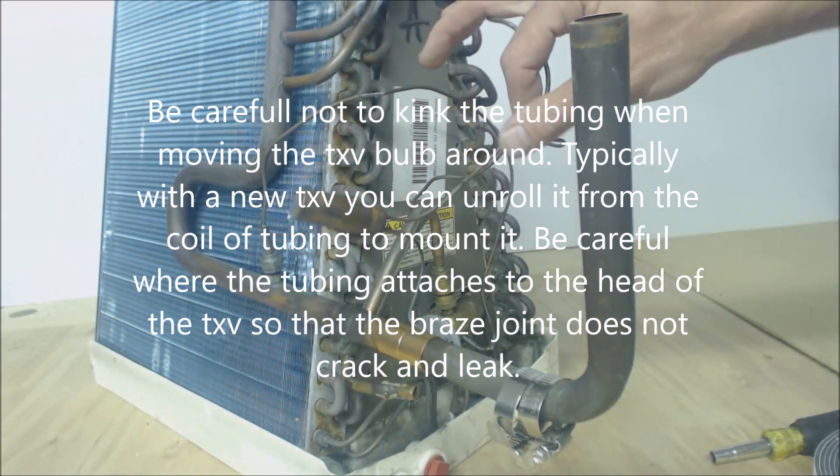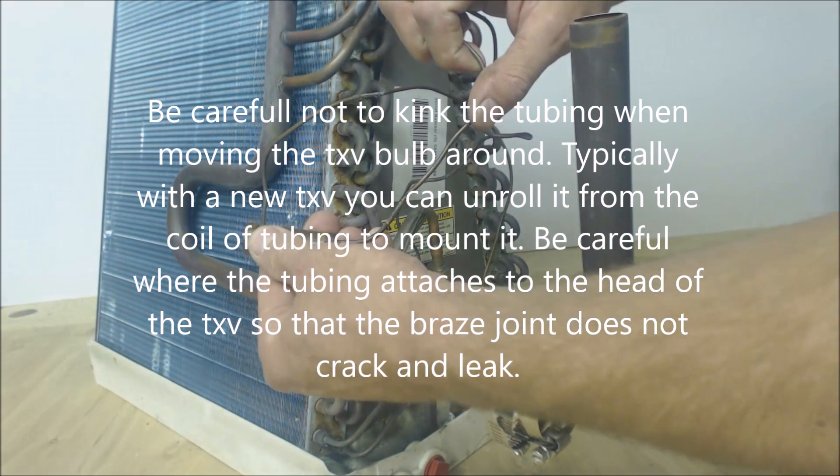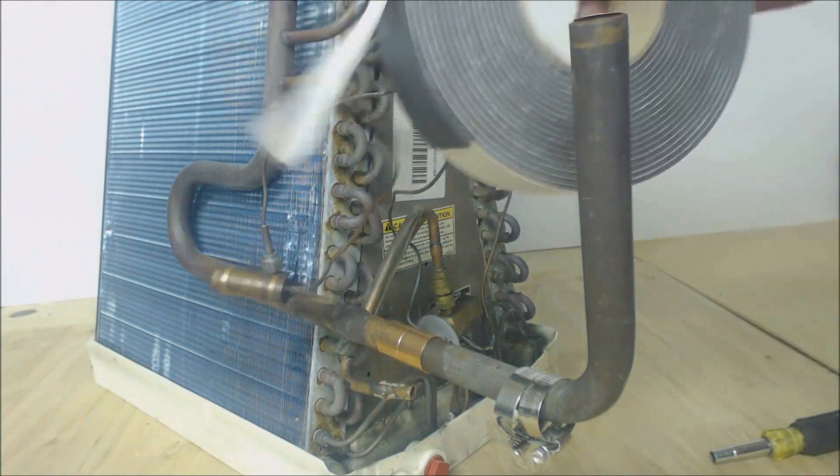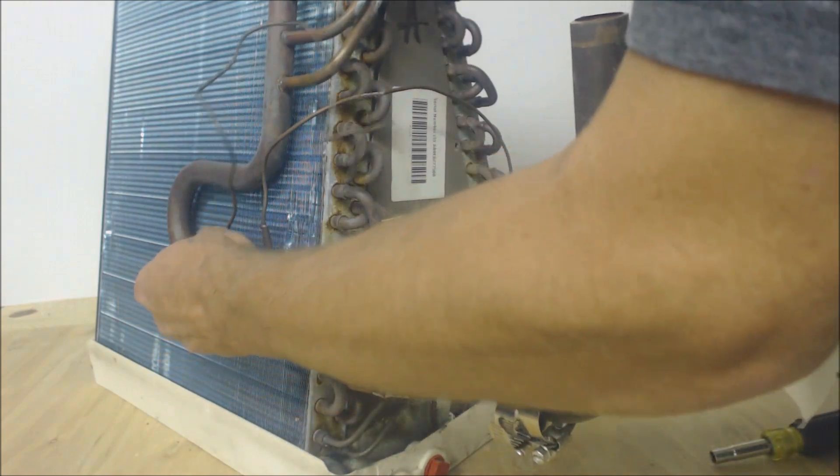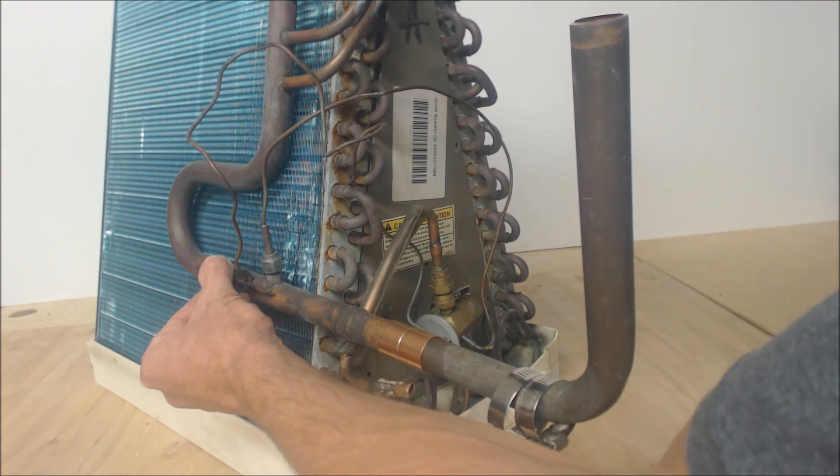Even inside the coil box, you're going to find that some manufacturers with factory installed TXVs, some are going to have the bulbs insulated and some are not. If you're doing it yourself, I would always typically recommend at least foam taping it, even if it's on the inside of the coil box, just to get the most accurate temperature reading possible.